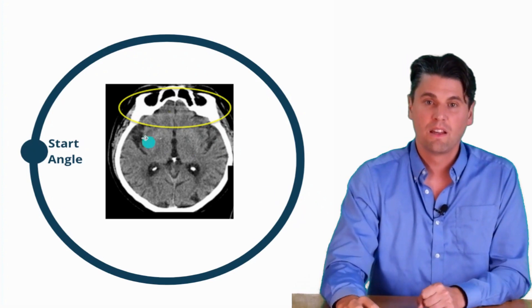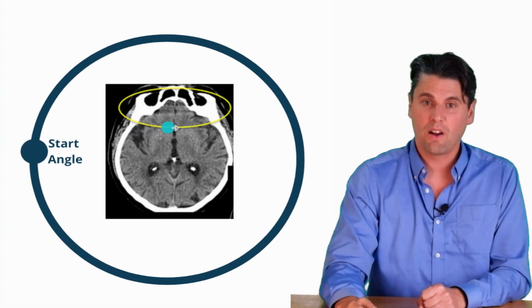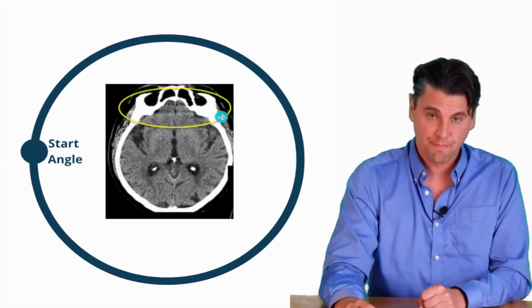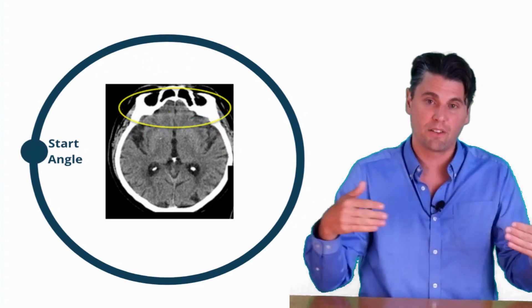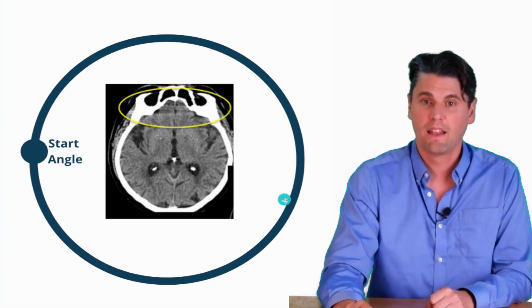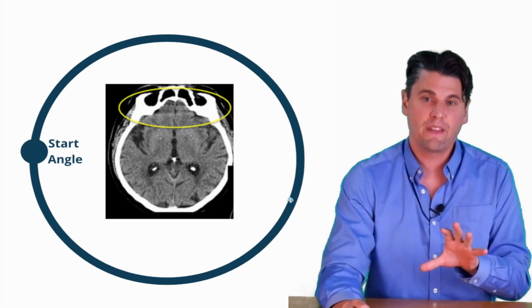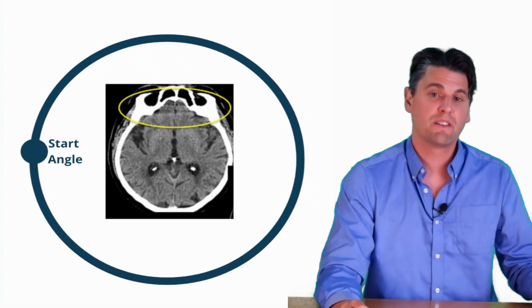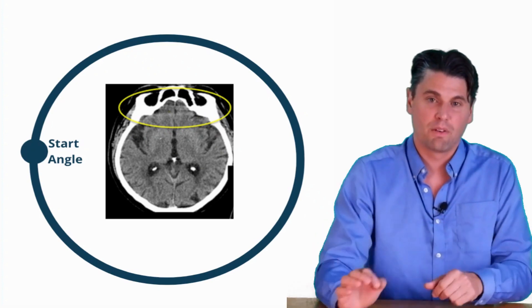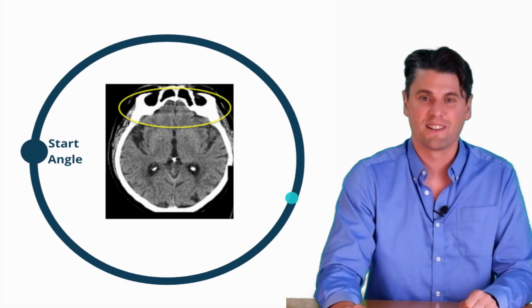So this gives you some kind of intuition as far as basic axial CT reconstruction. If in the case of head reconstruction, you had the start angle laterally on one side, you went all the way around the patient, and then the end angle is also right here. If you had motion in this direction, you could also see streaks, and they could look like this. So these artifacts here, like we talked about, are non-local because they're actually spreading out some of that artifact throughout the image volume in CT, which is different than an x-ray where that blurring is relatively local where there's motion.